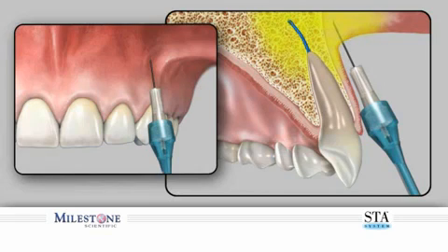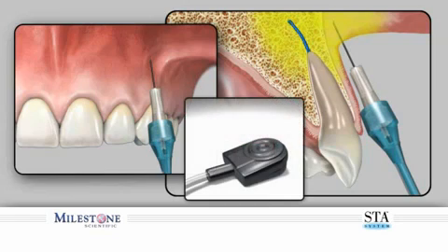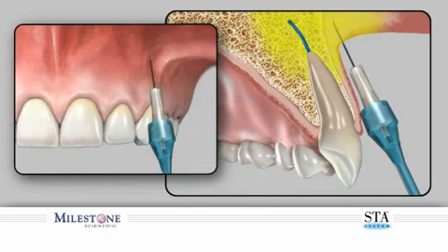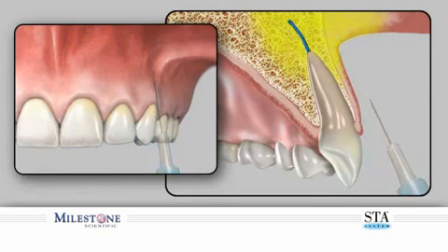When you have delivered the required dosage, you can remove the needle. To avoid anesthetic solution spray back into the patient's mouth, perform the following. While the needle is still embedded in patient tissues, depress and release the foot control pedal. Count 3 beeps after releasing the foot control and then remove the needle from within the patient's mouth. Direct the needle away from the patient, as a small amount of anesthetic solution may still be present.